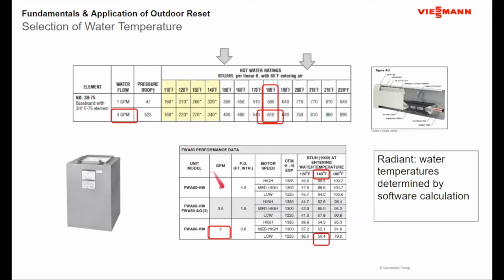When I do an air handler, I can select a flow rate, a blower speed, and then a water temperature. So let's say I decide that I want the supply water temperature to be 140 degrees, and I flow at 2 gallons a minute, there's 50,000 BTUs per hour. But from a design standpoint, when I start to look at putting the right size heat emitter to heat the building, or I'm putting enough heat emitter to heat the building, a lot of times the discussion is, this is a heat emitter I want to use, this is the water temperature, now let's see what combination works.